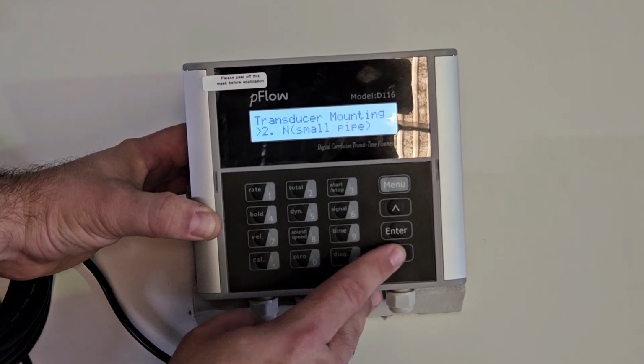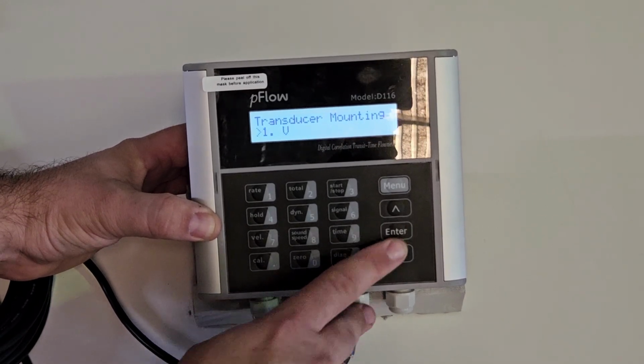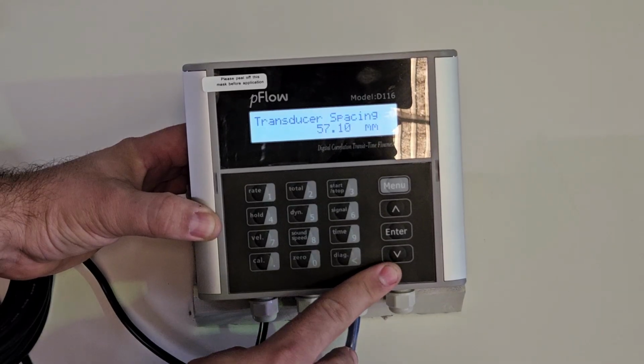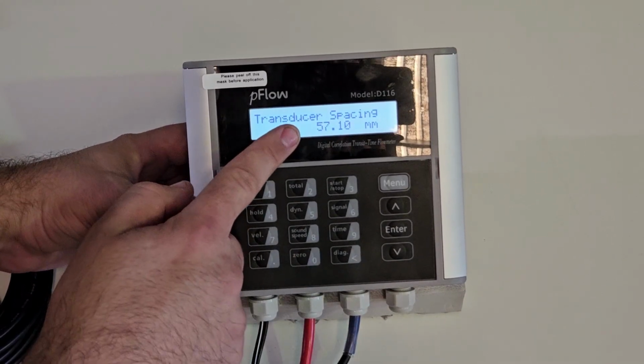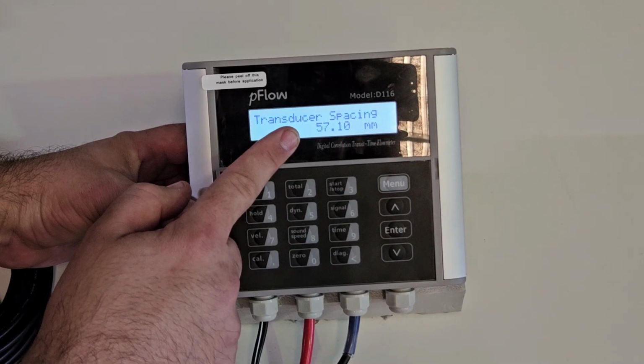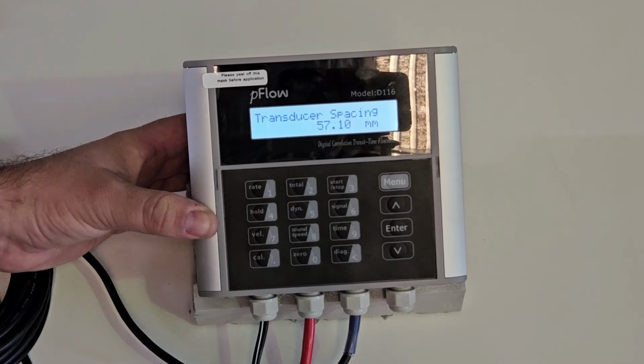Press enter, scroll the list of options, and enter to select. Now down one more time and you can see the required sensor spacing, 57.1 mm in this case. Take note of this to gap the flow sensors accordingly.